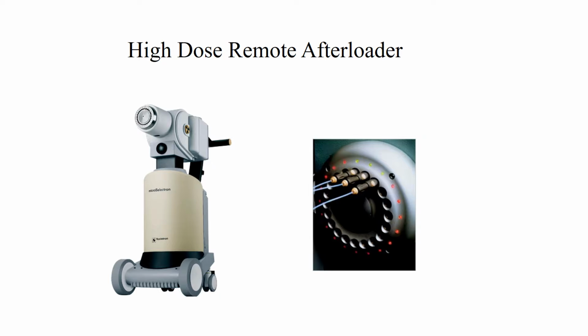Now with this machine, we can go ahead and add these catheter cables, as you see coming out of the machine on the right. It can do up to 26 of them, okay? You can then hook them to catheters that have been implanted into tissues via surgery. And then the machine will send that radioactive seed in and out of each catheter every time for the treatment, put it back in the machine, take it to the next catheter, bring it back out, and effectively treat the patient on an outpatient basis. And after this, depending on what the procedure is, after it's all finished, the patient goes home and they're not radioactive. And so therefore they don't have to worry about their loved ones and what they're doing to the environment around them.